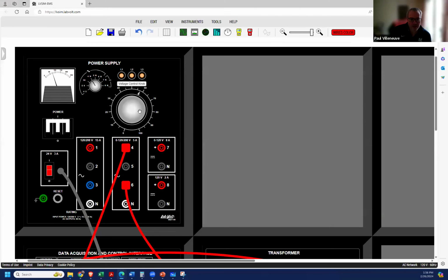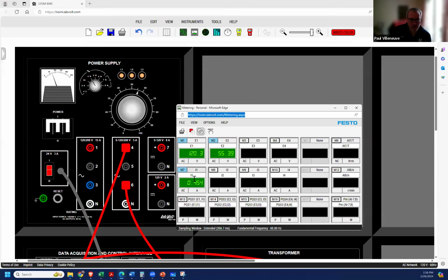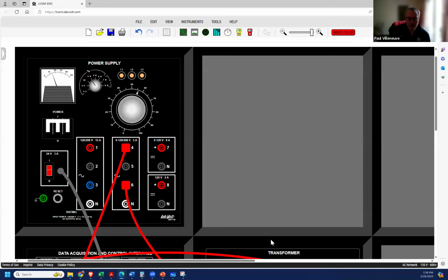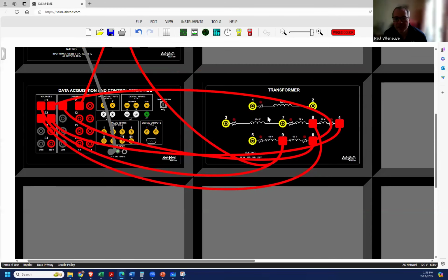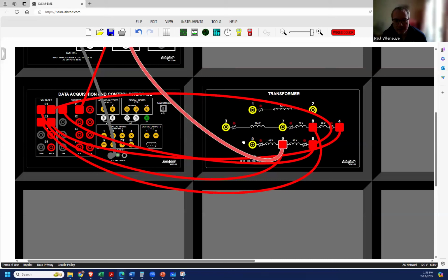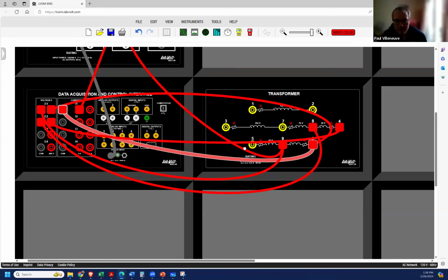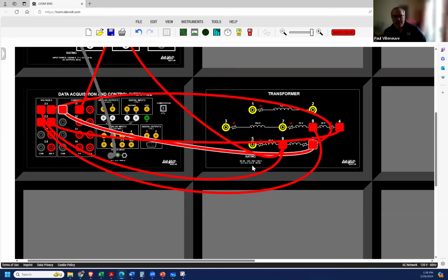So at 120 volts, more or less, look at the current now. It's 0.454. And if you remember from the nameplate of the transformer, we can run in that third winding about 0.5 amps without it overheating. That's the reason you can drive it to 120 volts, because the current transformer itself is rated for about 0.5 amp.